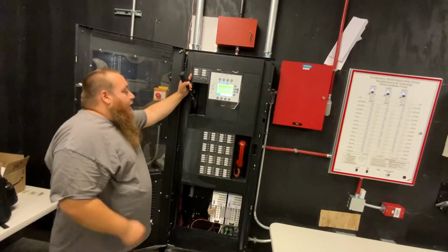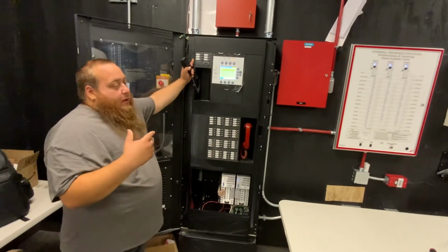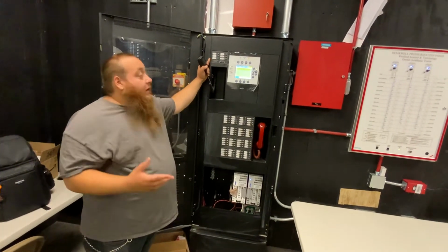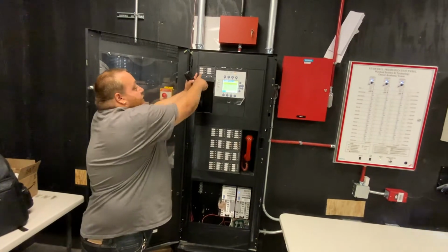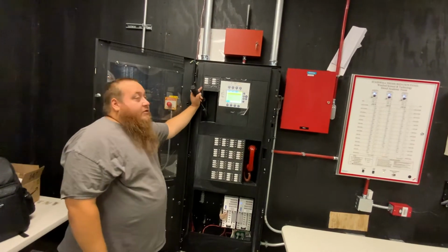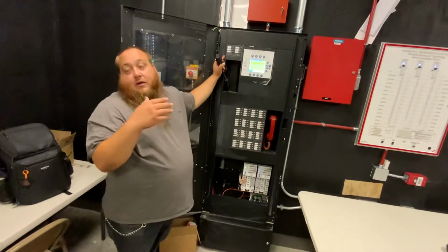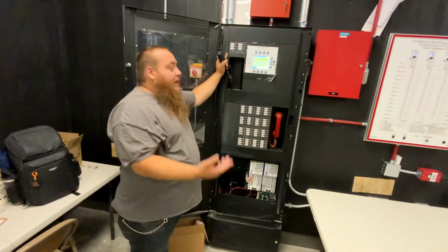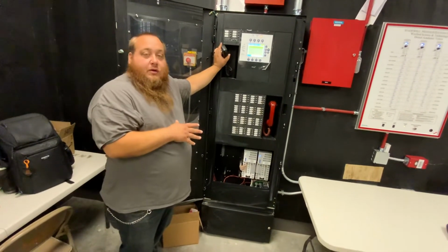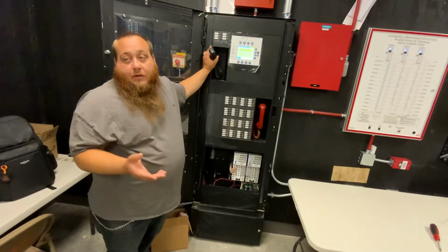Say there's a situation in the building and the system, it's not quite a fire alarm, but a pipe got broke or something smoldering didn't quite catch on fire and everything like that. You would hit that button and it would tell the whole building to get out. You have your all alert. Say there's a situation where it's not quite an emergency, but you might have to evacuate the building. Say a piece of equipment went down, anything like that. You would hit all alert and that would say, attention, there's a situation in the building. You don't have to evacuate. We're going to further investigate, but please be aware that there's an issue going on in the building.